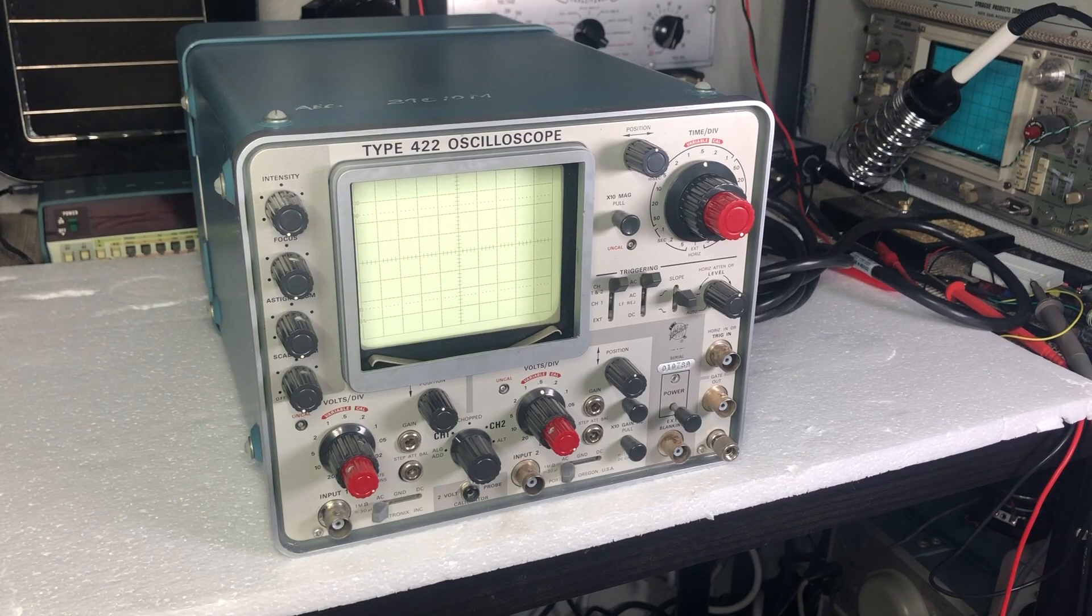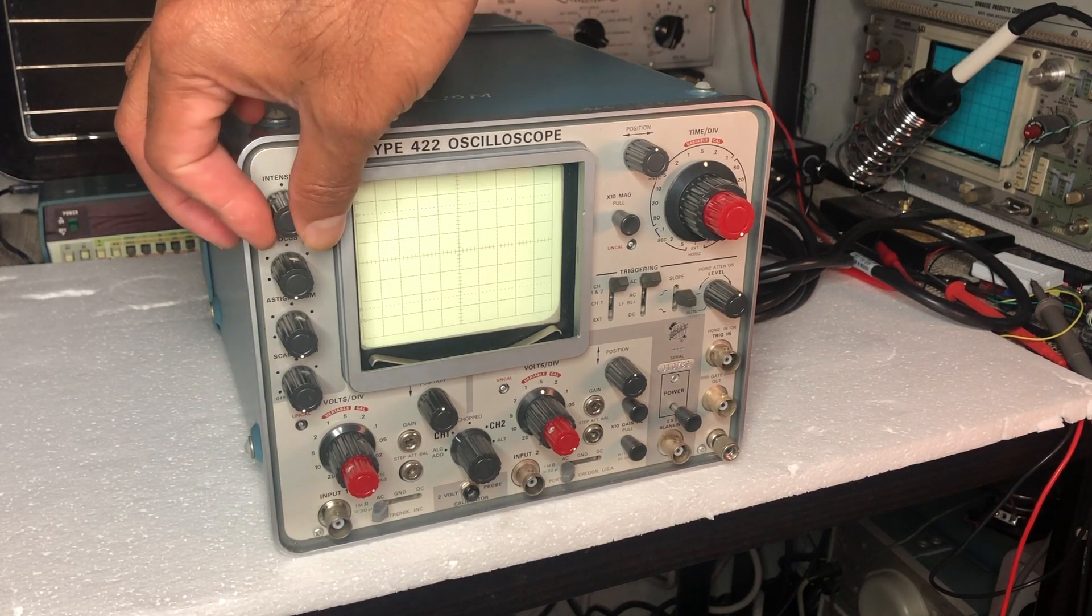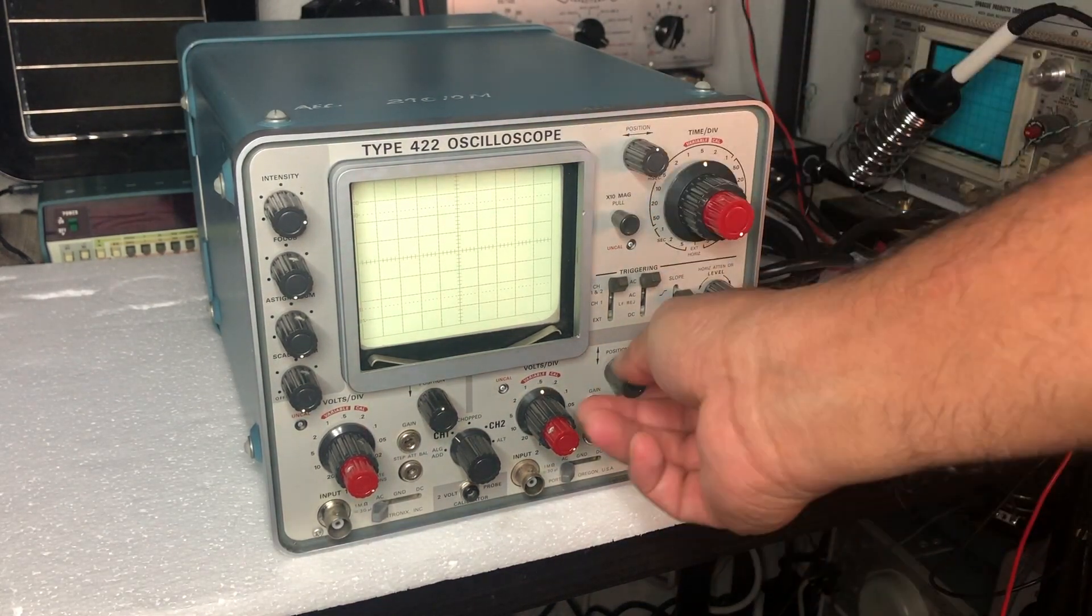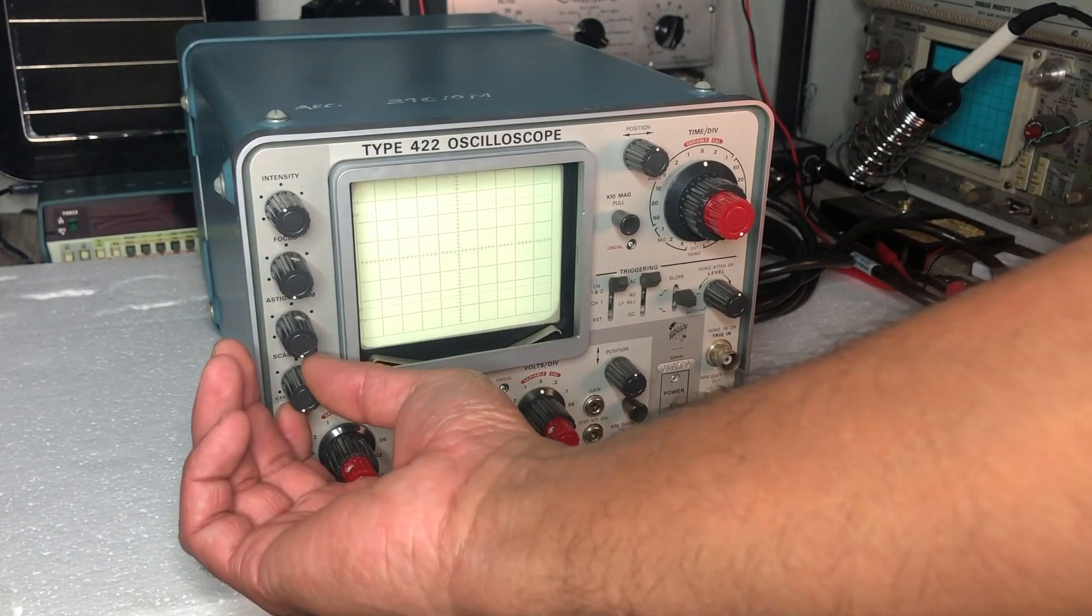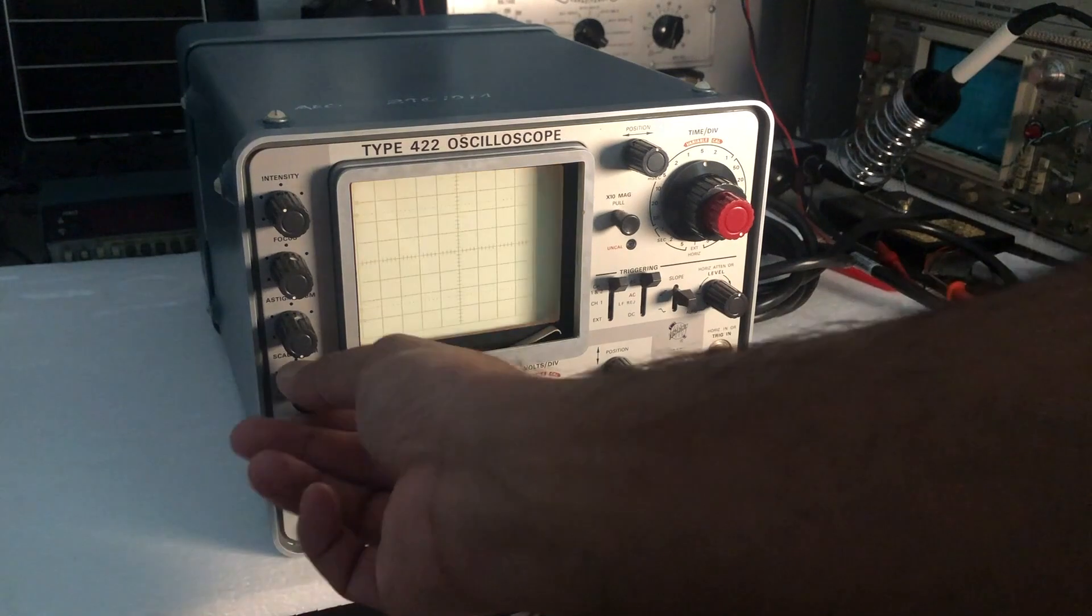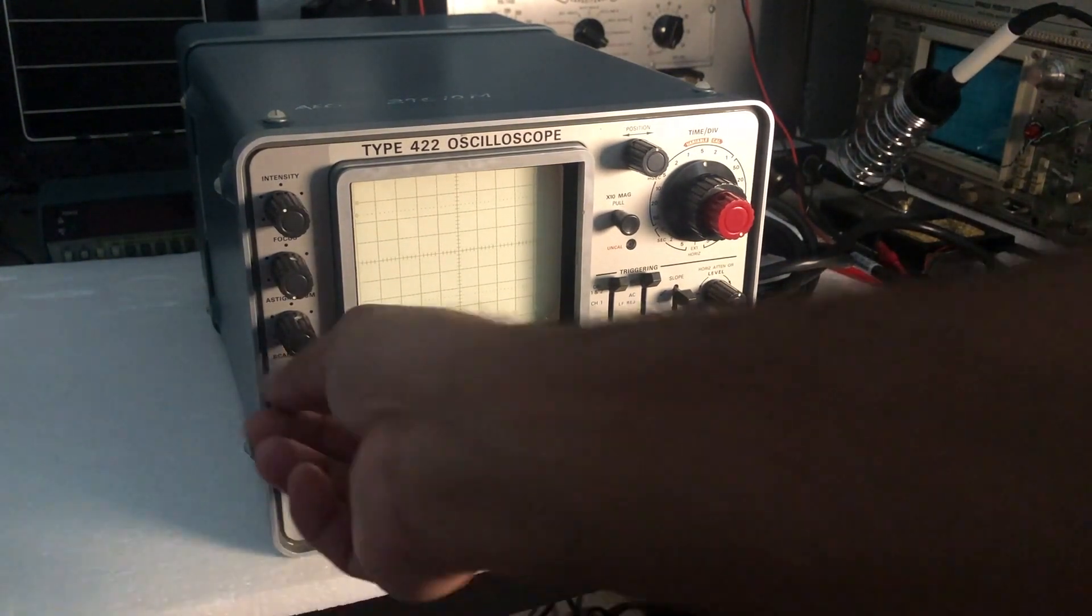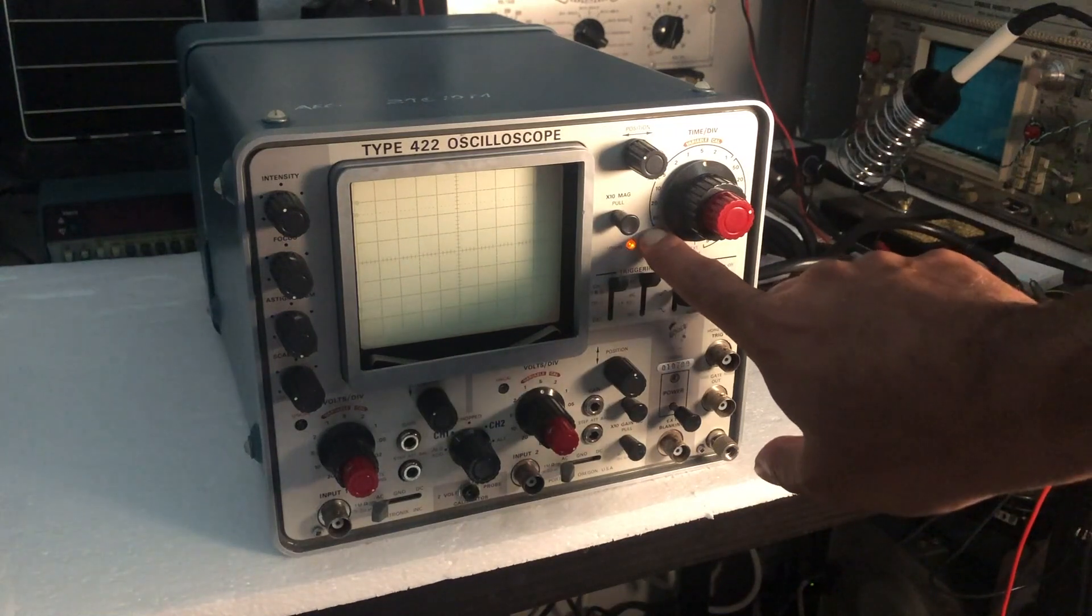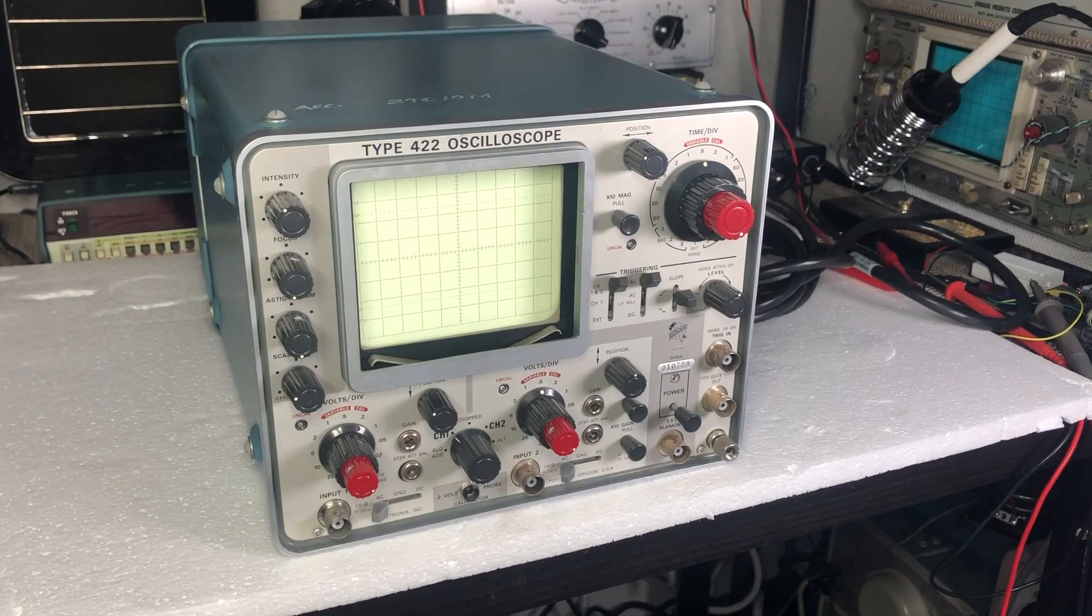Okay, I've given about 95 volts. Let me increase the intensity. Let's see if scale illumination is working. Oh yeah it is. Let me cut the light so that you can see scale illumination is at least working, but otherwise the unit is dead. The uncal indicators are coming up but no trace. It's dead. Let's get started.